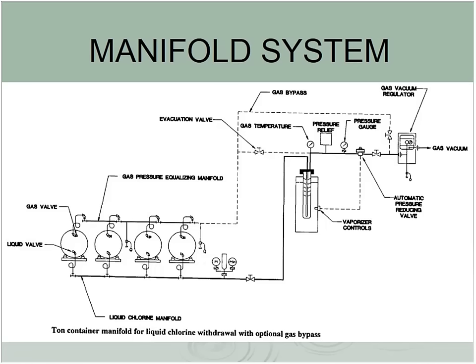Should there be a leak on one of these units, you never put water on the leak. If you put water on the leak, now you're forming hydrochloric acid, and a small leak is fast becoming a large leak. The reason that they're on rollers is if you have a leak on your liquid valve, you disconnect and you roll it so that it leaks gas.